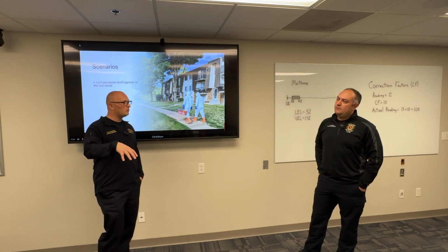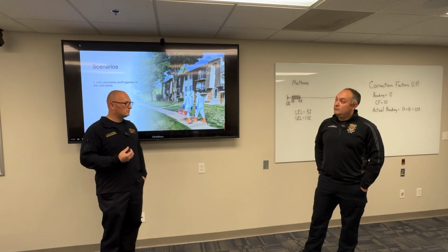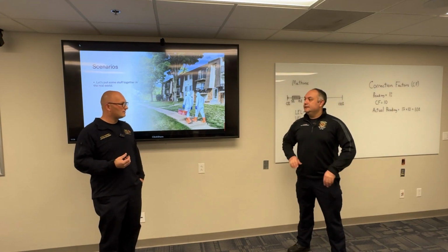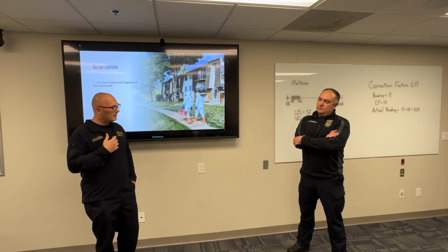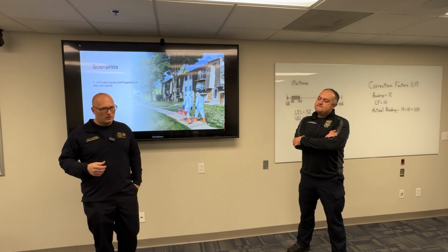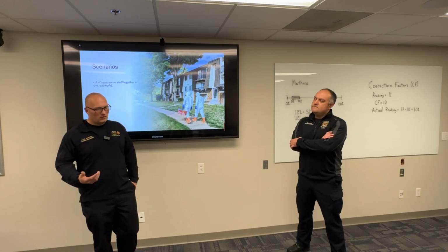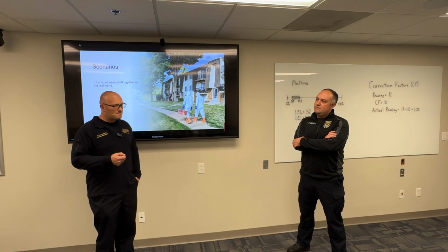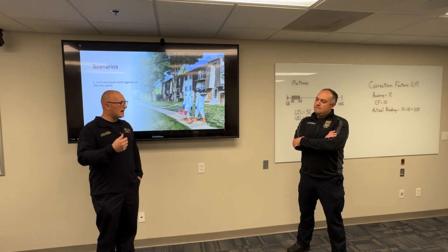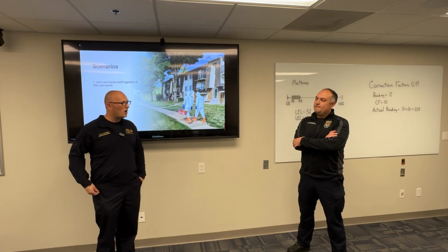When we get down to where the HVAC system is in the finished basement, it is a strong, bring-tears-to-your-eyes type of pungent, nasty odor. We shut off the HVAC system and start ventilating the house. As we snoop around a little more, we notice higher readings around the sump pump. We look in the sump pump and see this green film in there. We ask the guy right away, hey, did you dump something in here? What is going on?